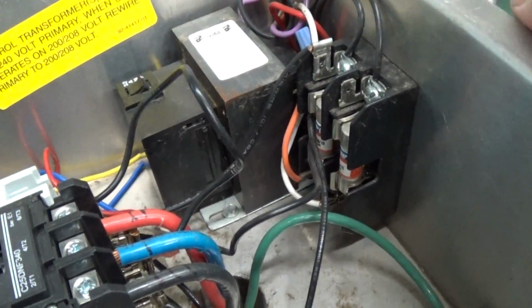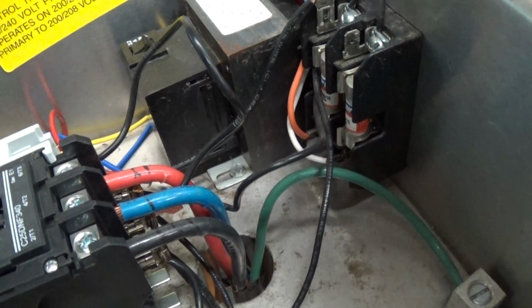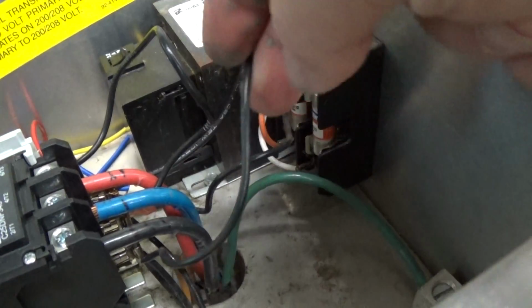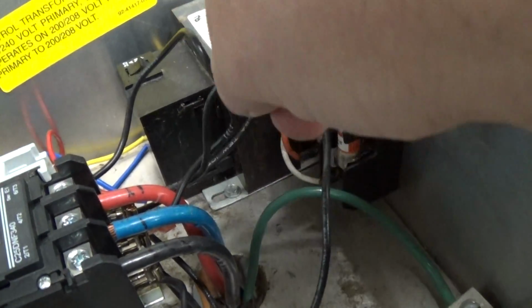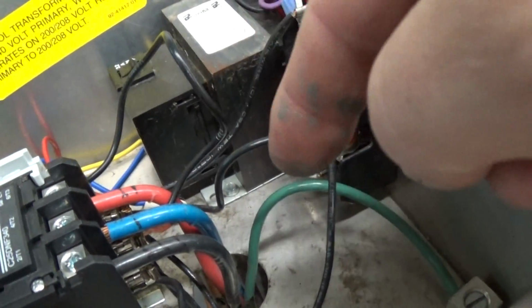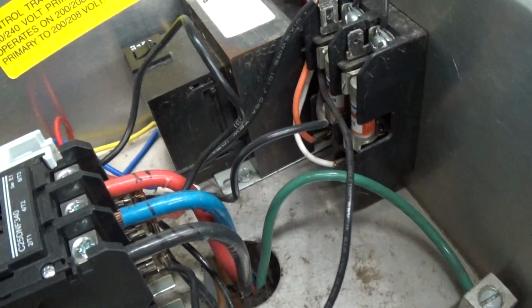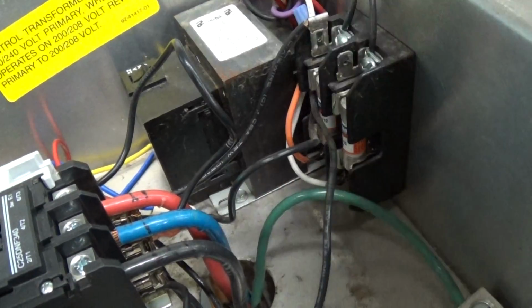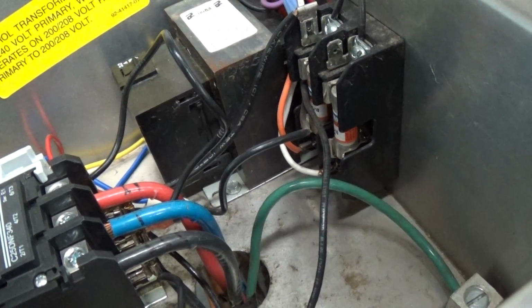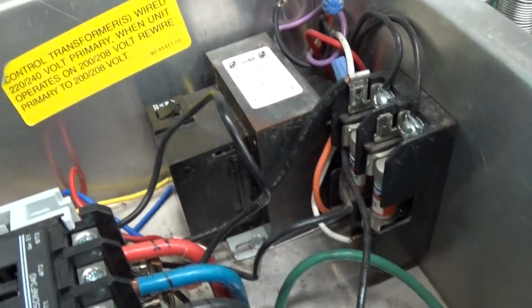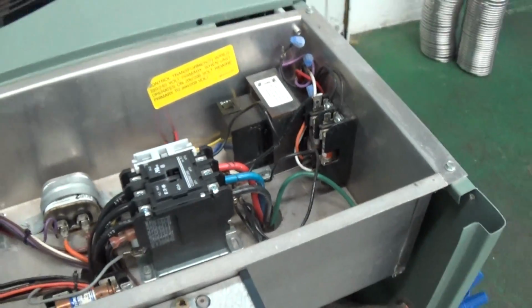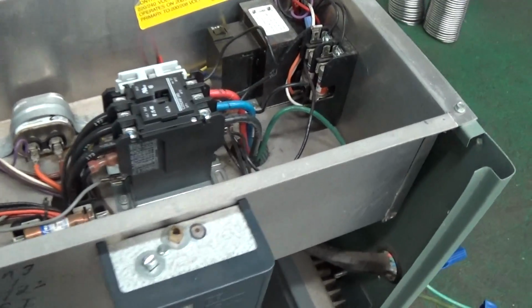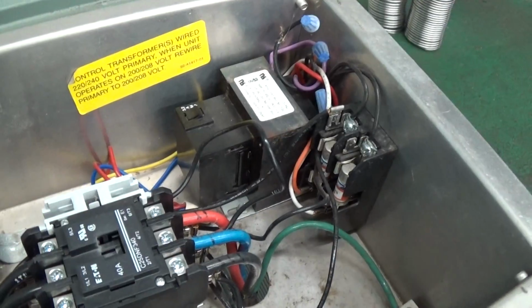There's two black wires. That's a single-phase transformer. There's two black wires to get your 230 or 208 volt single phase, just two lines off your main incoming power. There's one right here, and then the other one is right here. In this case, those two wires go to the leftmost and the rightmost of these three main incoming power connections. You need to make sure that whatever two lines these are connected to are not that wild leg. Otherwise you start blowing fuses or possibly transformers, that control transformer. That's the main thing. And double check with your electrician too. They'll basically say the same thing.